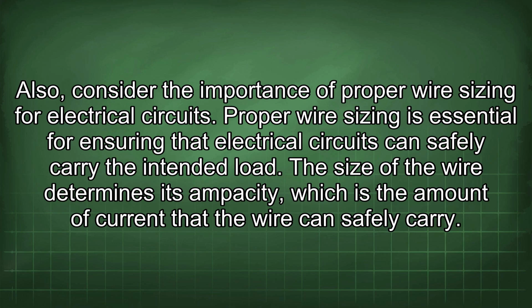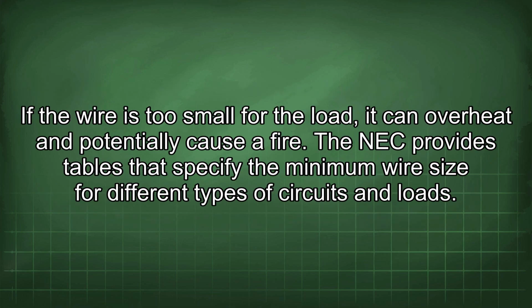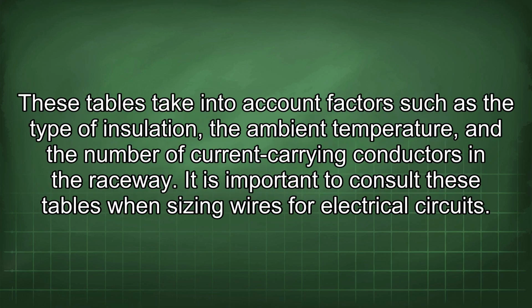Proper wire sizing is essential for ensuring that electrical circuits can safely carry the intended load. The size of the wire determines its ampacity, which is the amount of current that the wire can safely carry. If the wire is too small for the load, it can overheat and potentially cause a fire. The NEC provides tables that specify the minimum wire size for different types of circuits and loads. These tables take into account factors such as the type of insulation, the ambient temperature, and the number of current-carrying conductors in the raceway. It is important to consult these tables when sizing wires for electrical circuits.